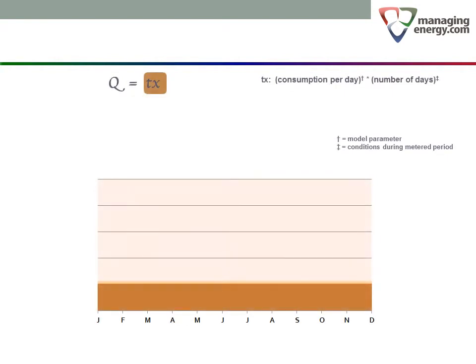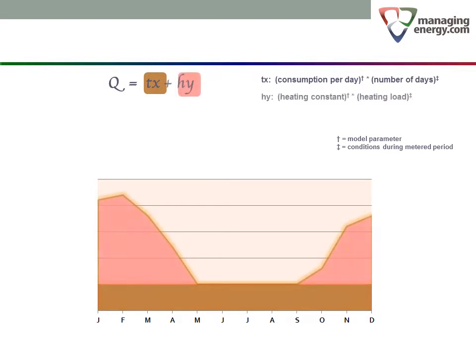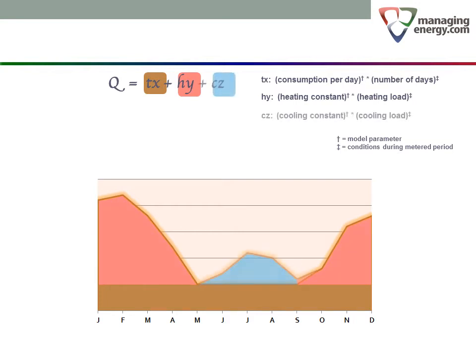In the second video in this series, we built up a mathematical model for the three components of energy consumption. We showed the base load as Q equals TX, where Q is the consumption for the period, T is the daily consumption, and X is the number of days. Then we added the heating component, the product of a heating constant H and the heating load Y during the meter reading period. The last piece was the cooling component CZ, consisting of a cooling constant C multiplied by the cooling load Z. Y and Z are derived from the local temperature conditions over the period.